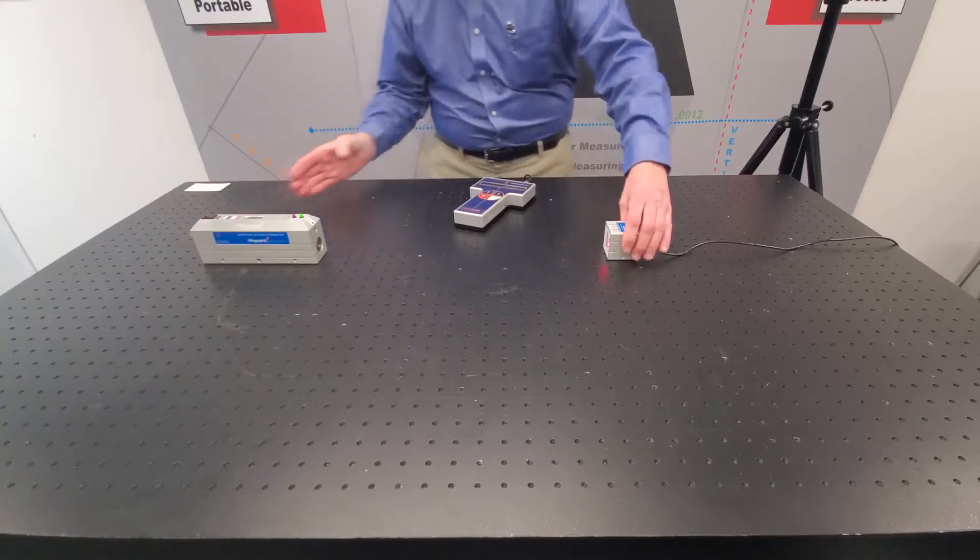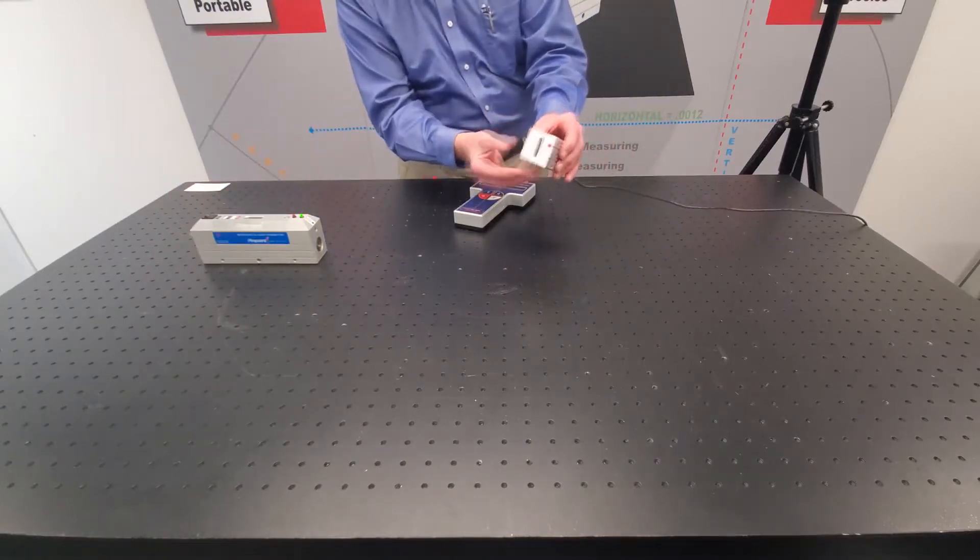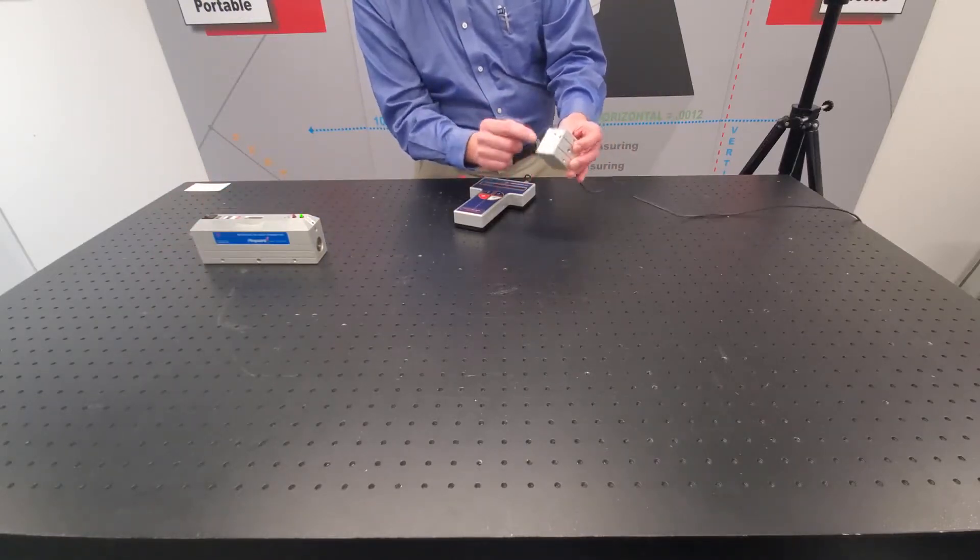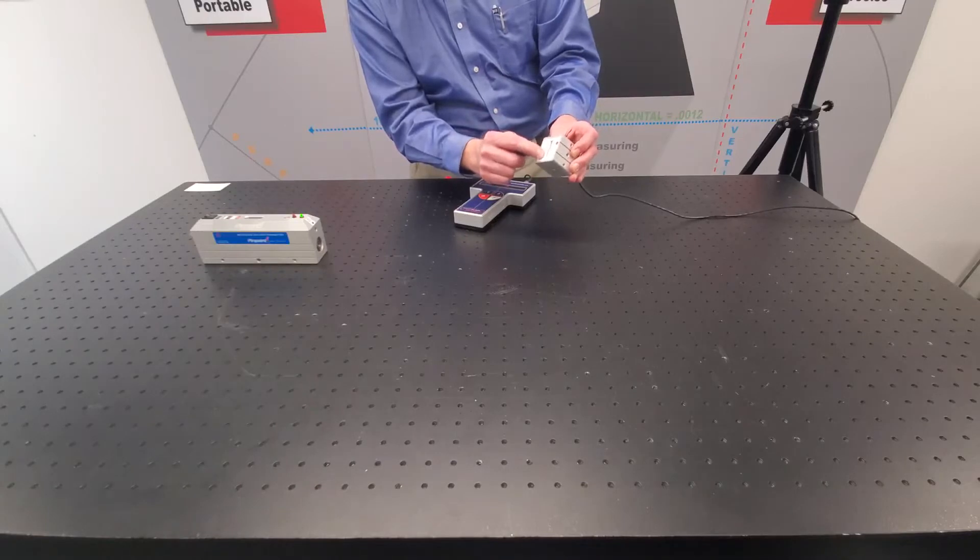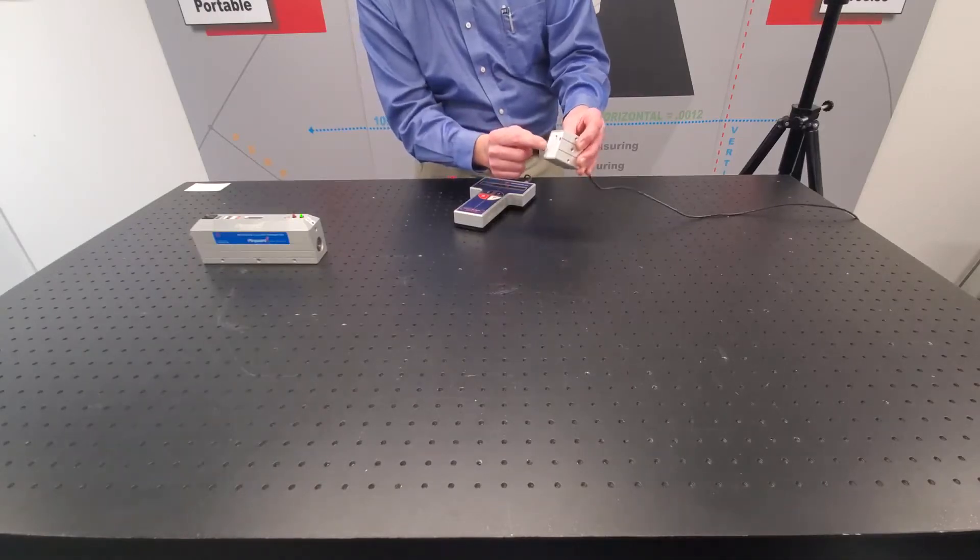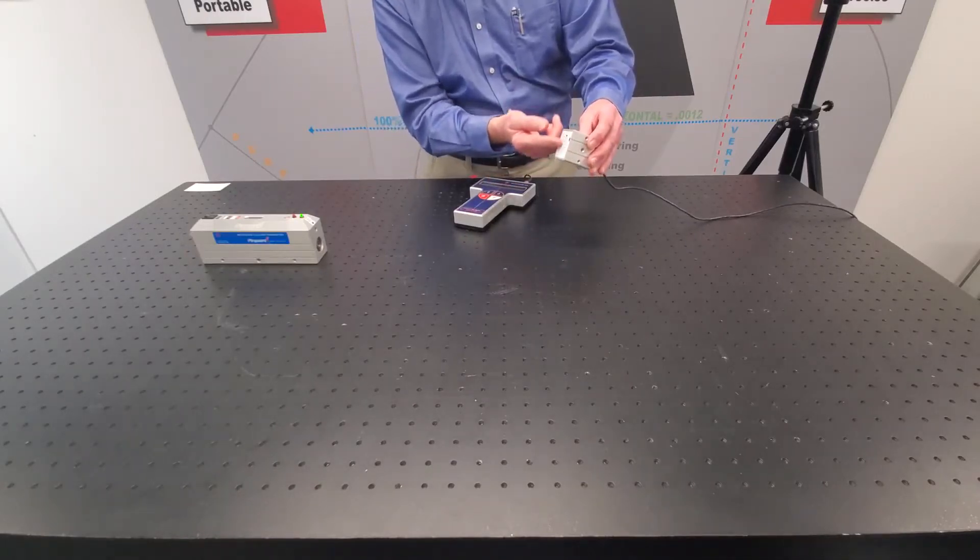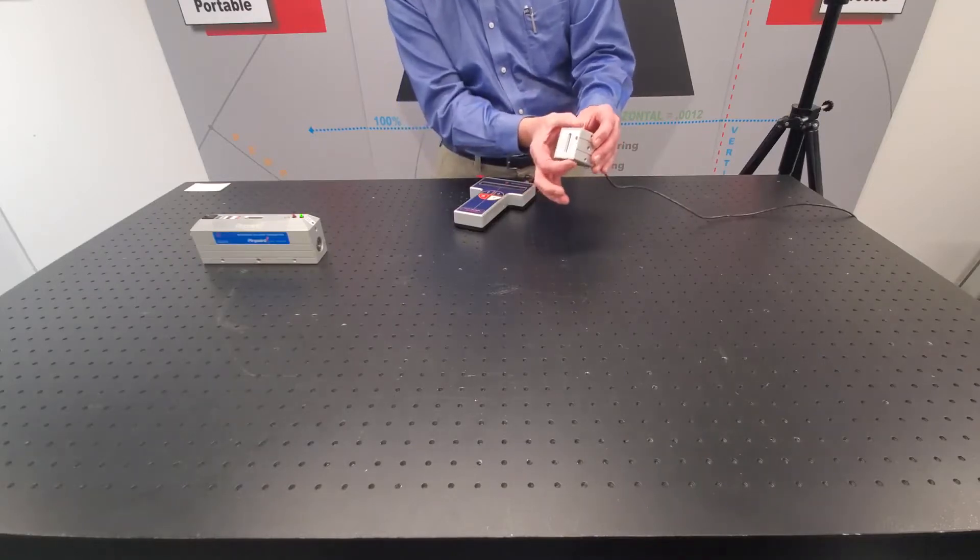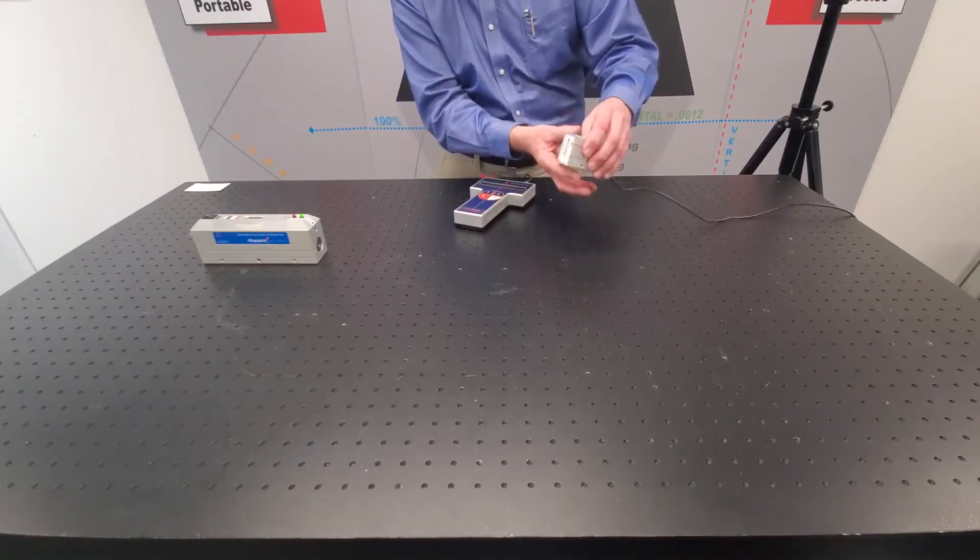The digital receiver is also a machined housing with mounting points on it and a long port in the end where the laser beam goes in, and an electronic detector measures precisely where that laser beam is hitting relative to the machined features on this housing.